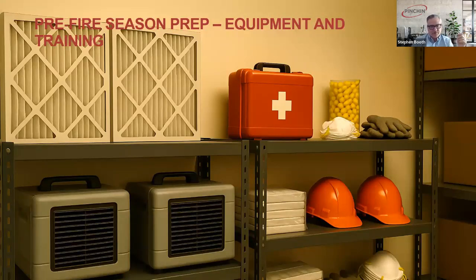It's important in advance to get supplies and equipment in place. Stockpile those MERV 13 or MERV 13 to 16 filters that are suitable for your units. Make sure you have the filter gaskets, the filter clips, sealing foam, all that kind of stuff in place. You'll want to have the portable HEPA air cleaners in place. Maybe spare filters for those if they're filters that you're maintaining and not that you're bringing in through a contractor. And you might want to look at stocking N95 masks for essential personnel that have to be in the building or working outside of the building during those really high smoke events where you can't fully control and keep those levels down below 30, below 35 micrograms per cubic meter range.